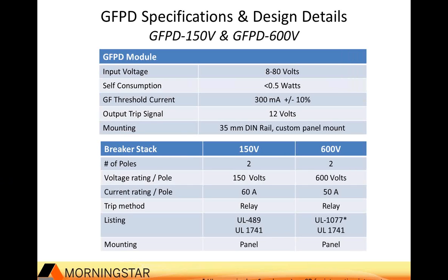Here's a rough idea of the general specs for the product. It does run off the battery, so it has an input voltage of 8 to 80 volts, very low self-consumption. The ground fault threshold current is 300 milliamps, so that's a much lower current level than these existing fuses that are used to detect existing ground faults. What we do is we send a 12-volt trip signal to the breakers, and then that will actually disconnect the entire system. And as I said, we have 150 volt or 600 volt versions. Relays are used to trip the breakers.